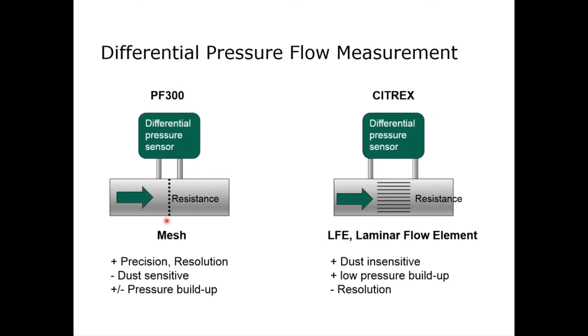In the case of the PF300, we use a mesh which is a highly linear resistance and it is also highly sensitive for small flows. In the case of CITREX, we use a so-called laminar flow element which is also very linear but a little less sensitive for low flows.